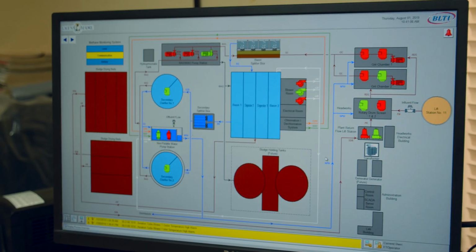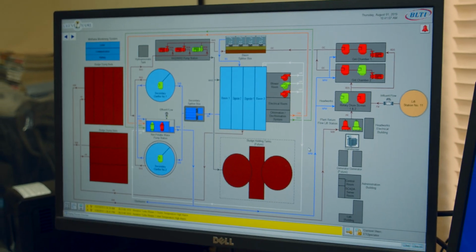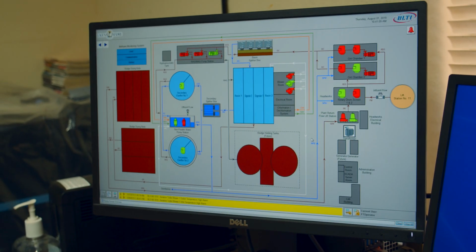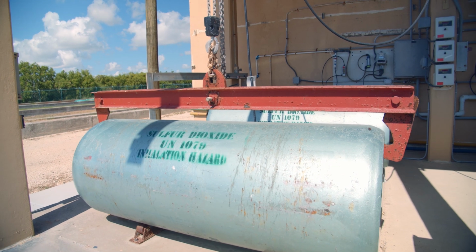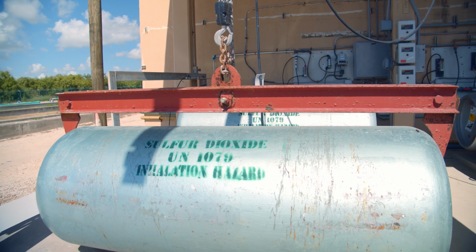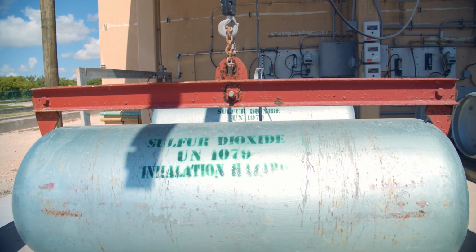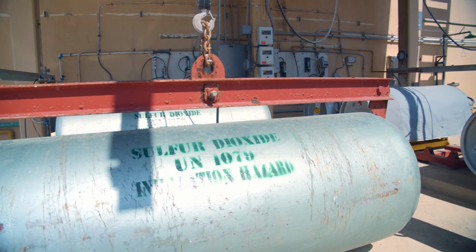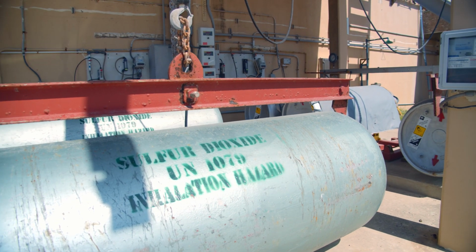At this step, we inject chlorine, give it the 20 minutes detention time to disinfect, and send it over a rectangular weir onto the next step of the process. Since there are strict regulations on releasing treated wastewater that has chlorine residual, the next process would be to dechlorinate. We utilize a chemical called sulfur dioxide that, upon making contact with chlorine, makes chlorine inert.